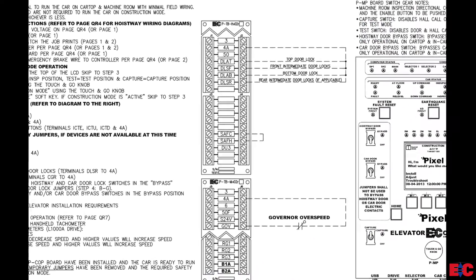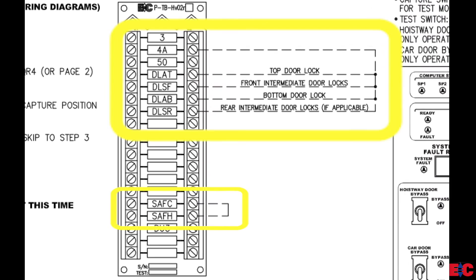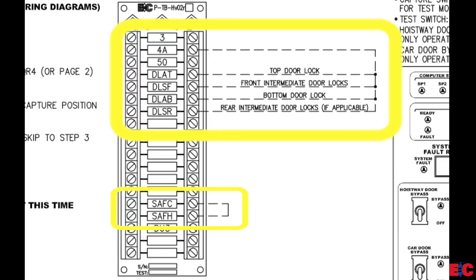On the hoistway terminal board, we want to install a jumper from 4A to all the door locks, DLAT, DLSF, DLAB, and to DLSR if you have rear intermediate locks. Then we want to install a jumper to our hoistway safety string from SAFC to SAFH.